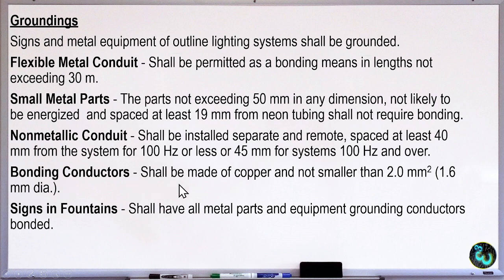Bonding conductor, so ito yung minimum 2.0 square mm or 1.6 mm diameter. Signs in fountains shall have all metal parts and equipment grounding conductors bonded. So yung lahat ng metal parts for signages na located on fountains dapat naka-bonded at properly grounded.